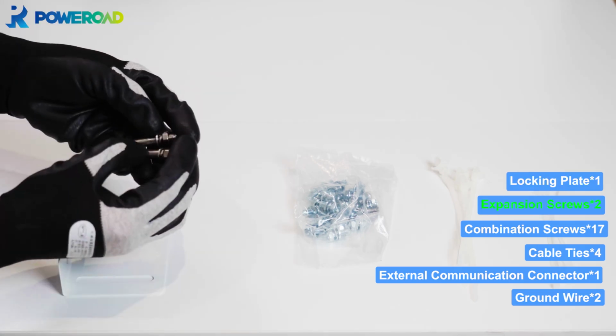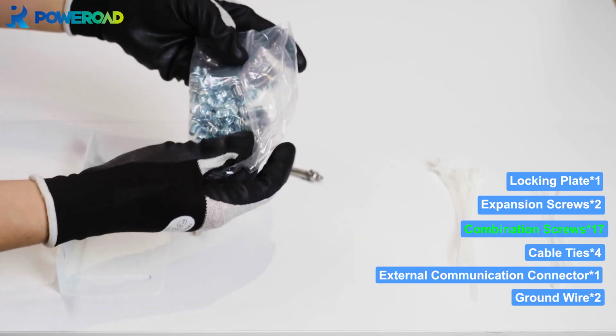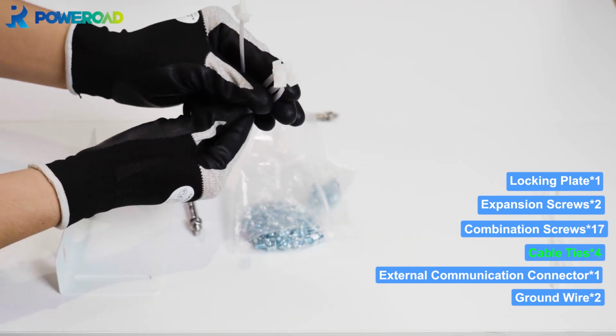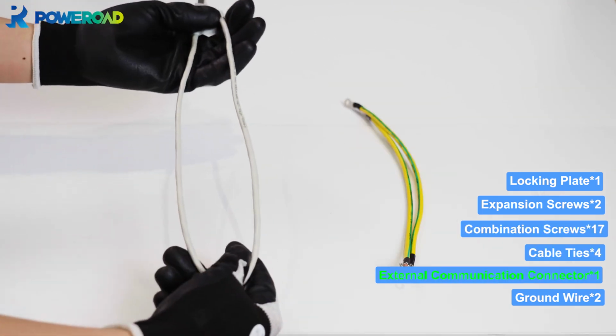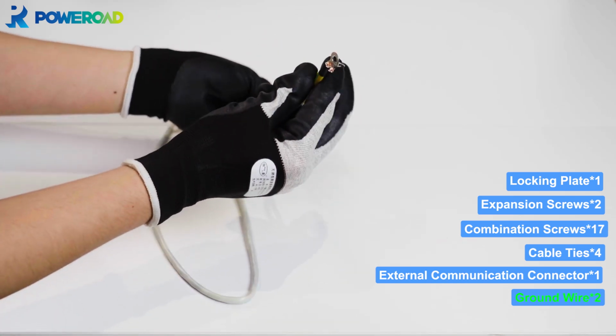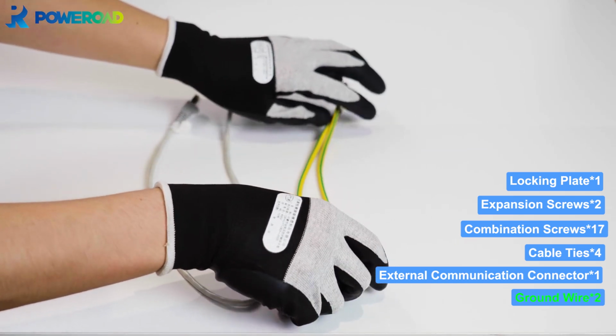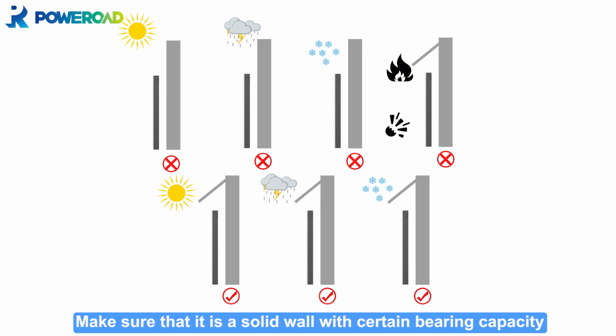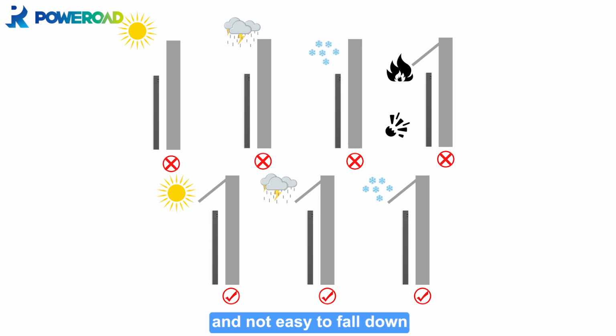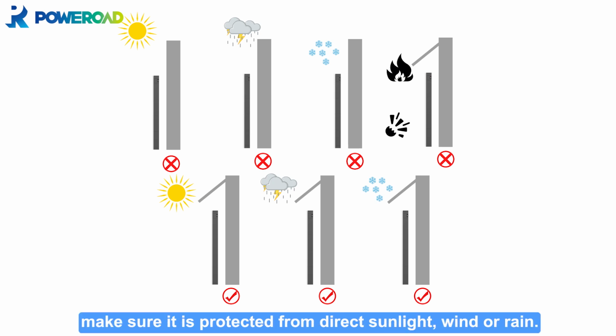Locking plate, expansion screws, combination screws, cable ties, external communication connector, ground wire. Make sure that it is a solid wall with certain bearing capacity and not easy to fall down. If the product is installed outdoors, make sure it is protected from direct sunlight, wind, or rain.